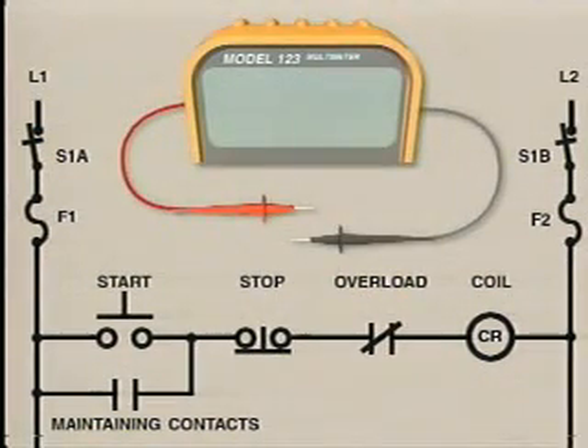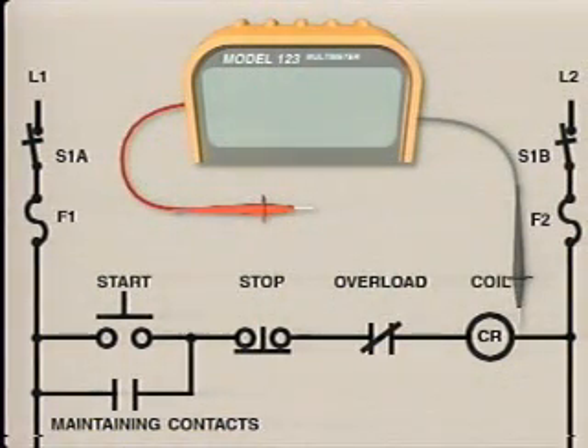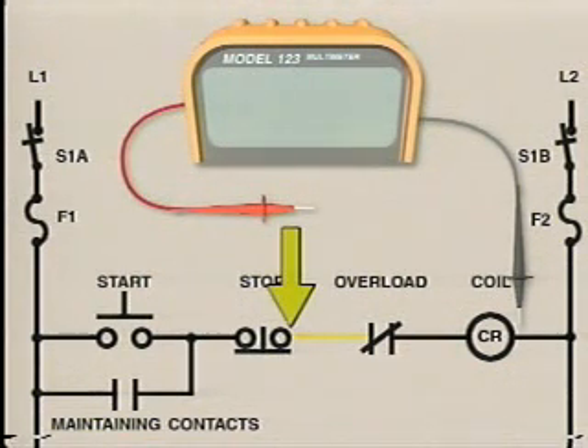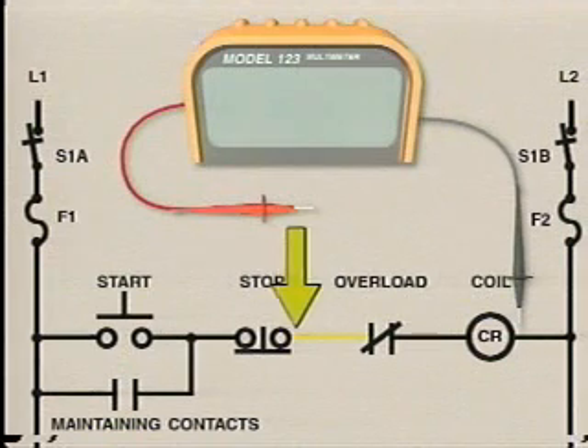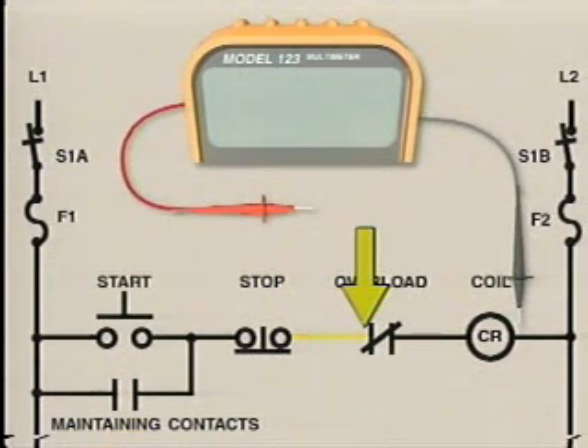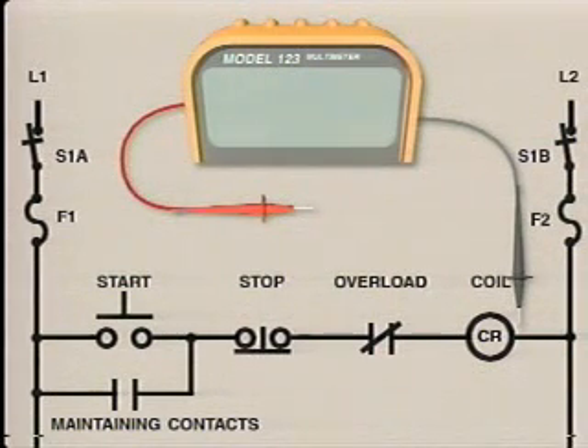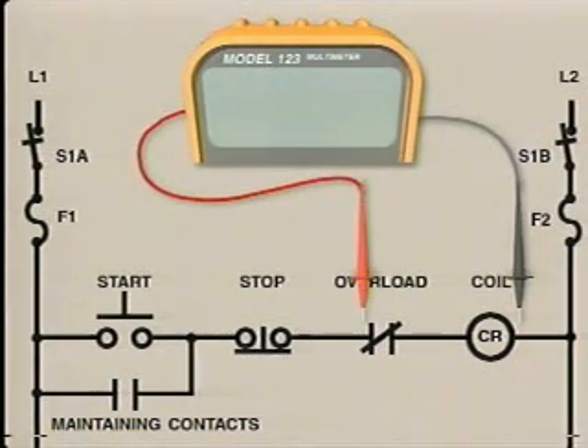The electrician decides to continue by testing for voltage inside the circuit. He'll use the right side of the coil as the reference point for his tests, since it's connected directly to line lead L2. To half-split this circuit, the electrician should test for voltage between the stop switch and the overload contacts. However, one end of the wire that connects these two components is in the push-button station, and the other end is in the control cabinet. Since the control cabinet is already open, the electrician decides to test for voltage at the overload contacts.